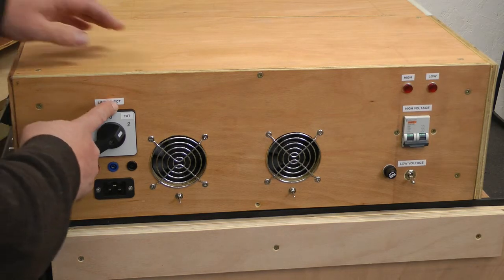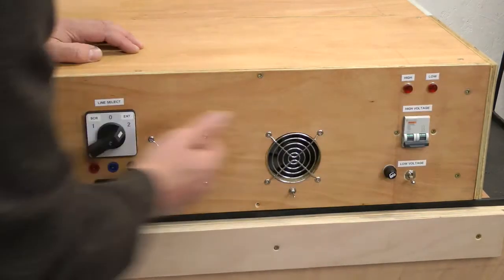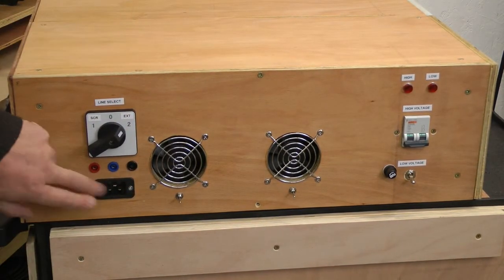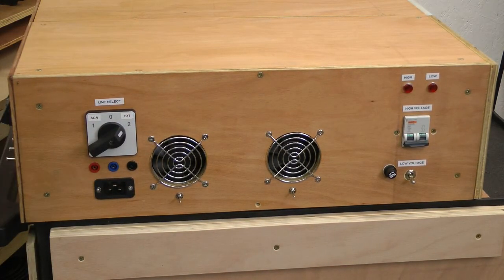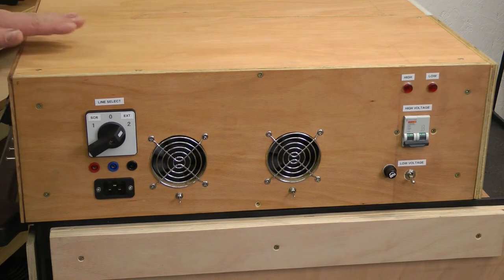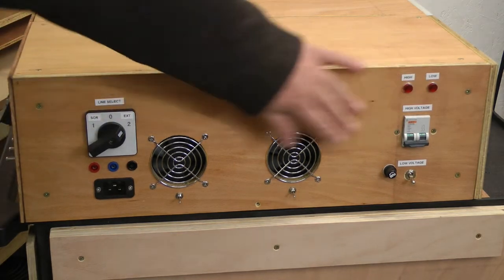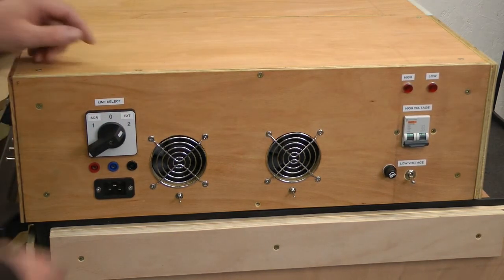This allows something, for example, like a variac to be connected or some other type of power control. So you are basically ignoring all the power for the transformers that comes through here and selecting an external supply. That's particularly useful when, for example, you want to do an experiment where you need to use a variac or something like that. Then you can easily get access, and that then feeds the power through to the control system in exactly the same way as it would come through from the SCR.